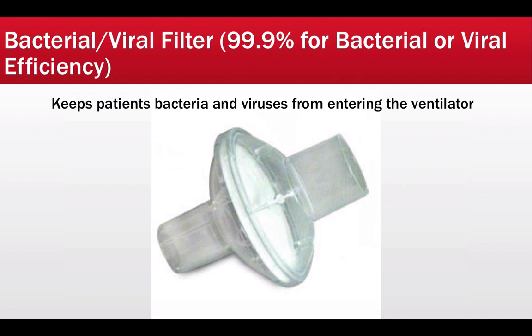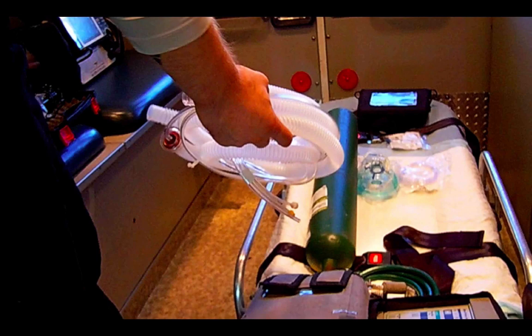The manufacturer also makes a bacterial and viral filter with 99.9% efficiency for bacteria and viruses. These filters keep the patient's bacteria, viruses, and pathogens such as tuberculosis from entering the ventilator and contaminating the unit. Here I have three video clips demonstrating the most vital aspects of circuit connections.